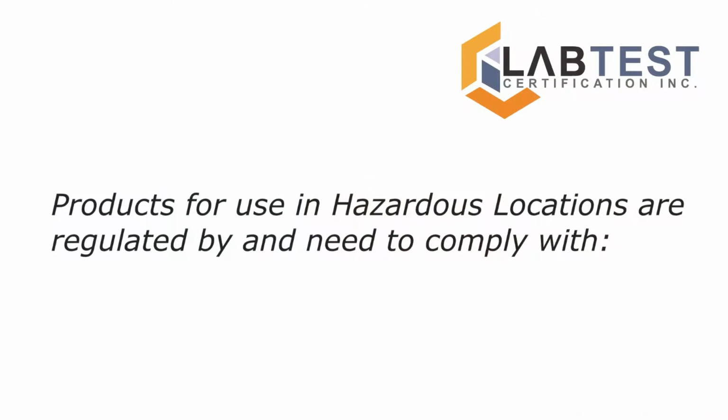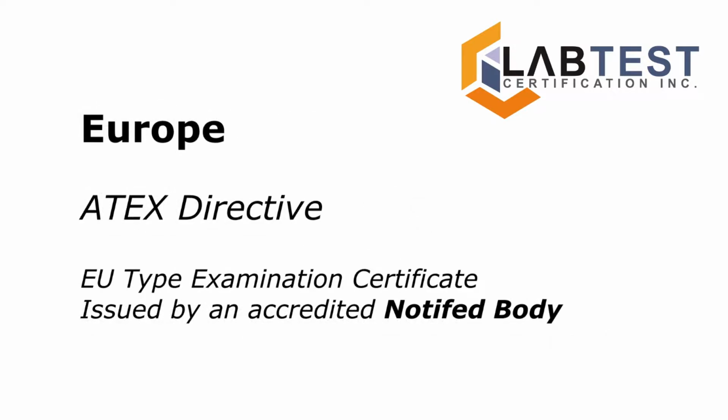Regulatory systems in North America are somewhat different from the ones in Europe, and the main difference is that products meant for hazardous locations in North America need to bear a certification mark from an accredited and approved certification body. And in Europe, that certification will need to be issued by a notified body. They're basically the same thing, but the names are different.